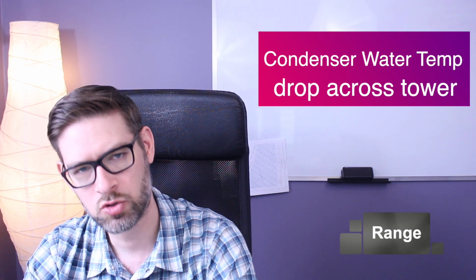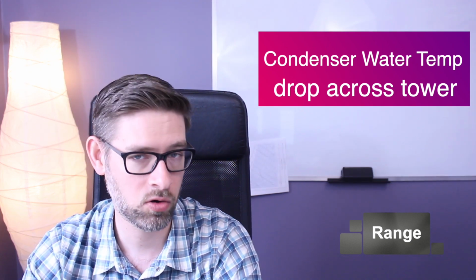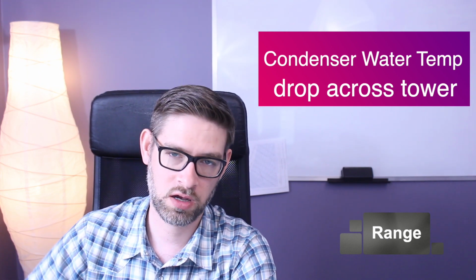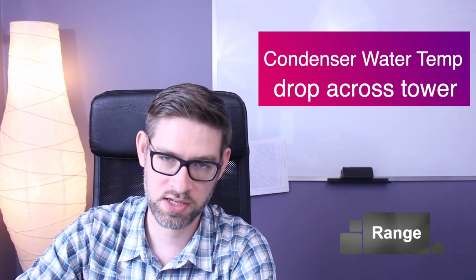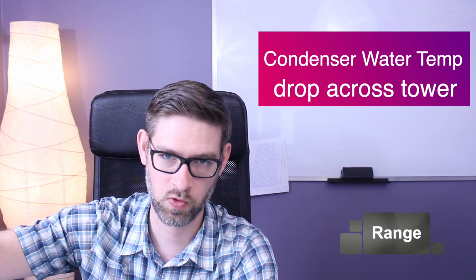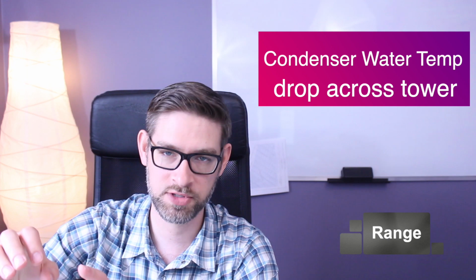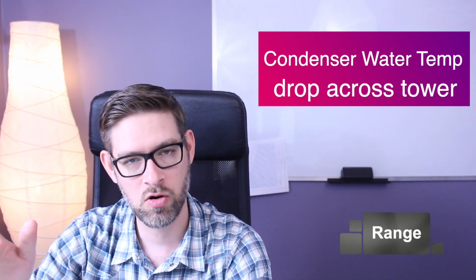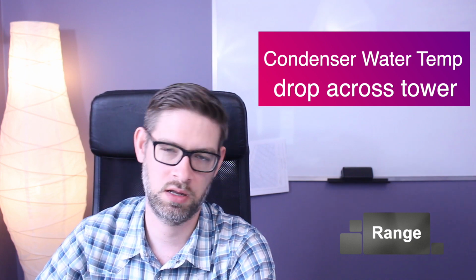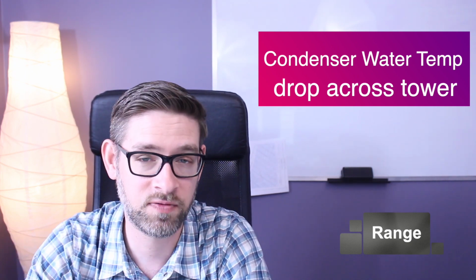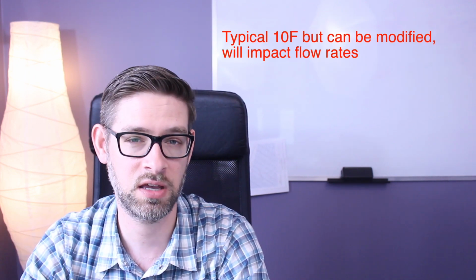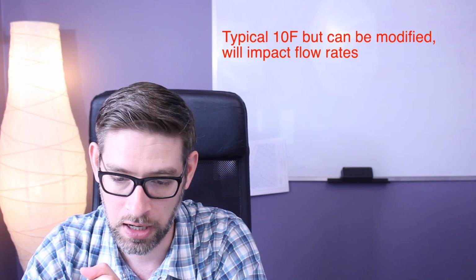temperature. Next term that we're going to discuss is range, kind of like a delta T. So the condenser water temperature drop across the cooling tower or the fluid cooler. As the condenser water comes into the cooling tower, the evaporative cooling process rejects heat from that condenser water and the cooler condenser water drops into the basin. So what is the delta T, or the difference between the water in the basin and the water coming into the top of the tower? That's defined as the range. Now, typically in comfort cooling applications, that range or that delta T is about 10 degrees Fahrenheit.